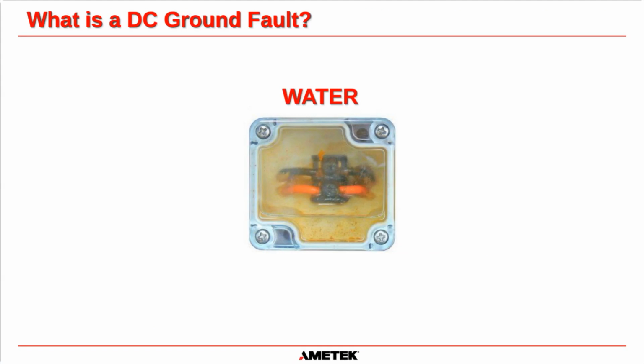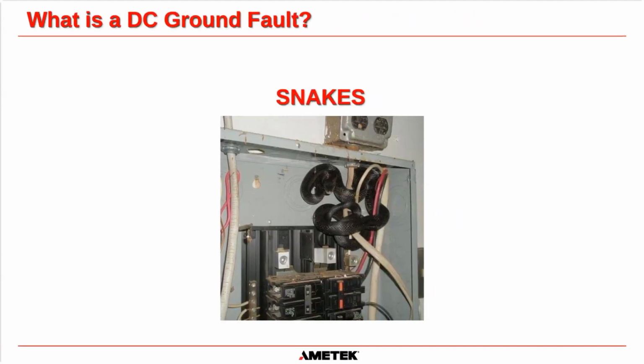Water. This actually looks like this yellow stuff is resin. That is not resin. There's actually water inside this junction box. Okay, and obviously you have your two terminals here. If that water has impurities in it, then that will cause a short across those two. That will probably blow a fuse, but if not, it may just cause one of those cables to go down to ground somehow. Okay, good example. And snakes.